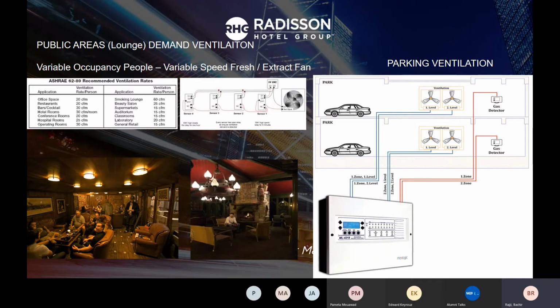So we distribute the sensors in this area, and they measure the air quality, the CO and the CO2 level, and according to them, we can control and adjust the fresh air and the extract from inside this area. Let's say if you have only 2 people smoking, no need to run the fan on full capacity. I can go down because the air quality sensor shows now there is no heavy concentration of CO and CO2. We can reduce. I can first save energy on the fan amps, the same as the case of the kitchen, and also I can save on the air conditioning, because, you know, extracting air conditioning air which is at 22 or 23 degrees and throwing it out is a cost of money as well. So always, this is from my experience, what I'm sharing.